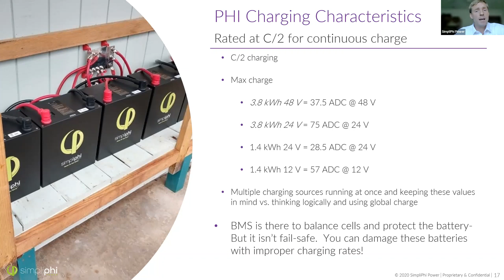So, the charging characteristics: you want to limit the charge rate on various devices. About every MPPT out there will offer you the ability to control the rate of charging. Inverter chargers are not so good at this. You can set most inverters to limit the charging rate, but their settings are a little less reliable, and we'll have problems occasionally after a firmware update where the settings got switched back to default by accident, which can damage batteries. So we want to make sure to get things set up properly and be careful with these settings.